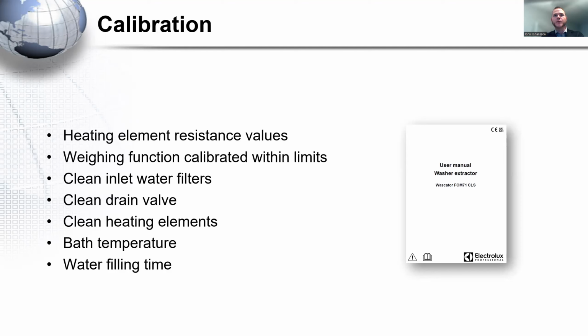And the reason for having it as a calibration point is that resistance heating elements tend to change in resistance over time. So it's a good thing to control at least once a year. The weighing function should be calibrated. There is a fully detailed procedure for this in the user manual. And it should be made sure, and preferably be traceable, of course, to a known weight.